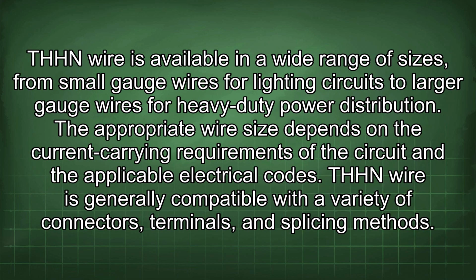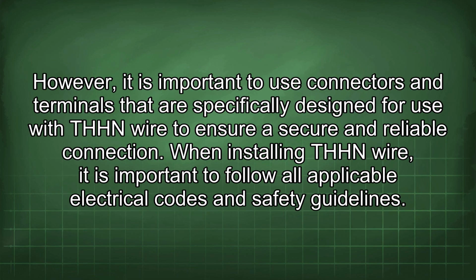THHN wire is available in a wide range of sizes, from small gauge wires for lighting circuits to larger gauge wires for heavy-duty power distribution. The appropriate wire size depends on the current carrying requirements of the circuit and the applicable electrical codes. THHN wire is generally compatible with a variety of connectors, terminals, and splicing methods. However, it is important to use connectors and terminals that are specifically designed for use with THHN wire to ensure a secure and reliable connection.